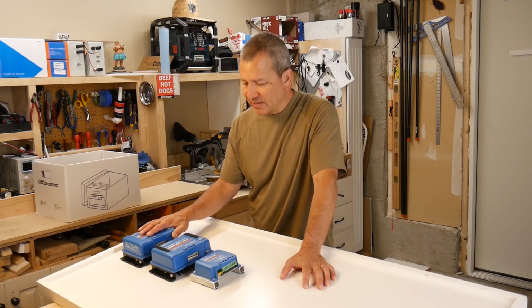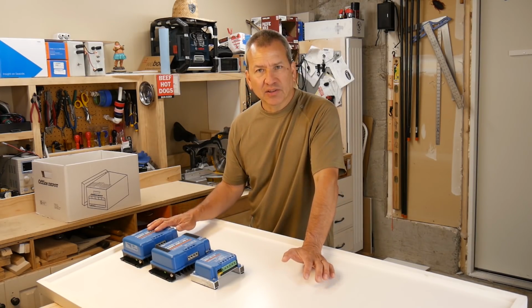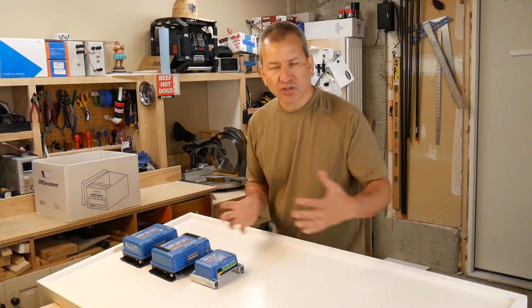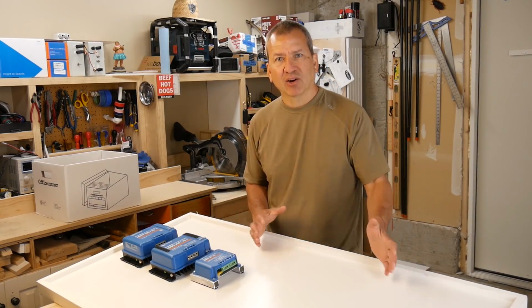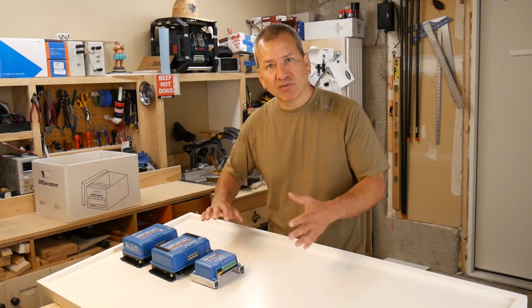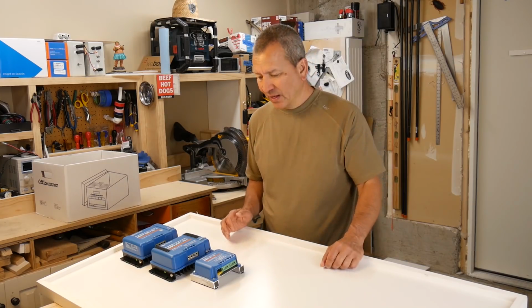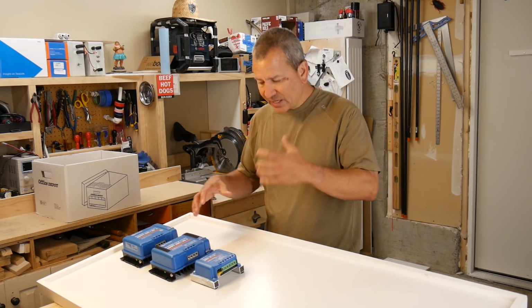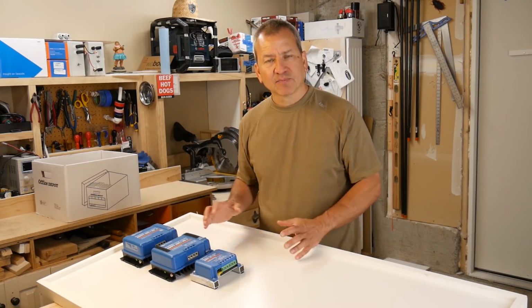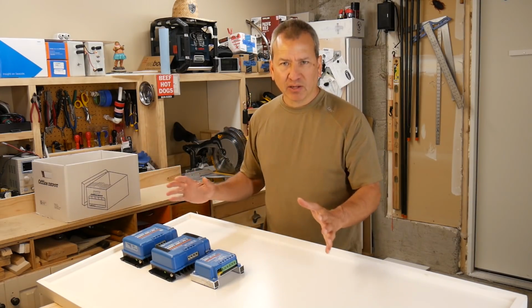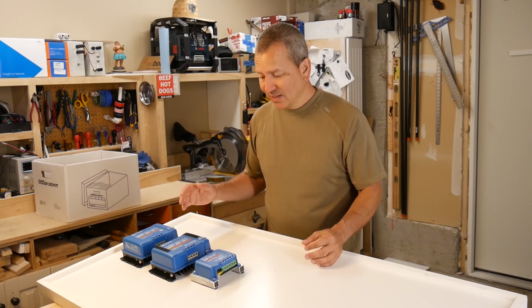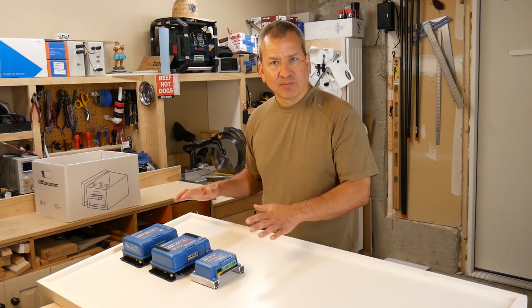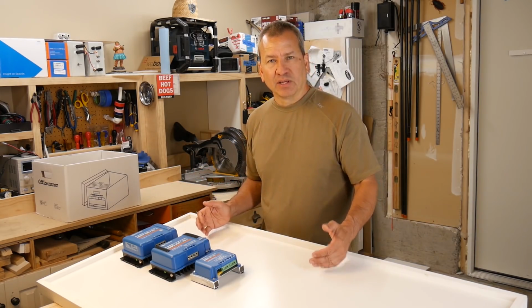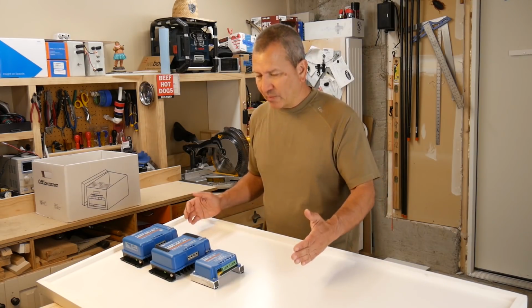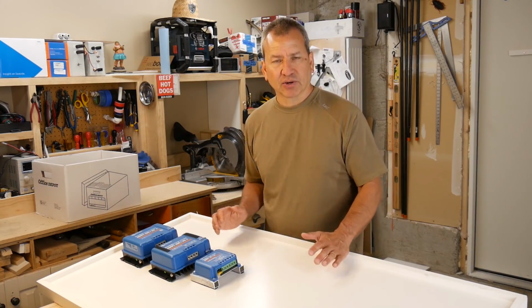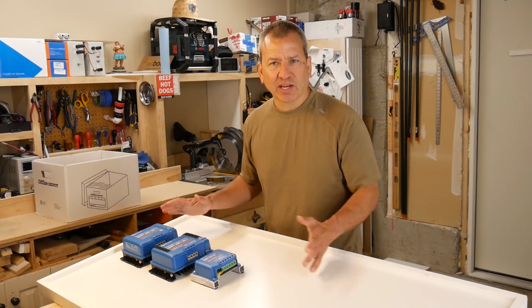The first thing is that we have to set all of these up so they're all charging the battery bank in parallel, meaning the outputs all need to be connected in parallel. I also want to keep the cable lengths the same, so the parallel setup works best when they're all about the same distance from the battery. They'll be physically located in the same area, so when I run my cables, I want to make sure the lengths are about equal.